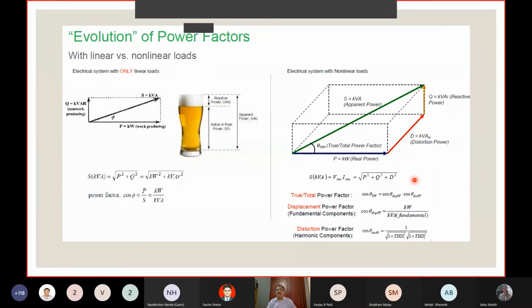In some factories, I show one case study where this distinction was clearly visible to us. But in a few cases, in Andhra Pradesh or Telangana where there is kVAH billing, our meter was configured to capture the distortion power, but the electricity board meter, the trivector meter, was not configured, or their software was not configured to capture the distortion power. So they continue to address only the displacement power factor, PF only. The harmonic distortion power factor was not addressed. So that also happens, but when you go for an audit, look for a clue as to how this kVAH is going to be impacted because of the distortion factor.